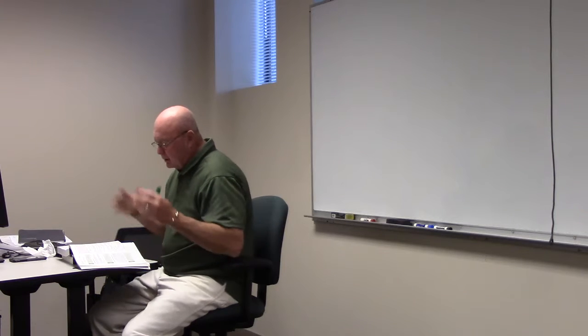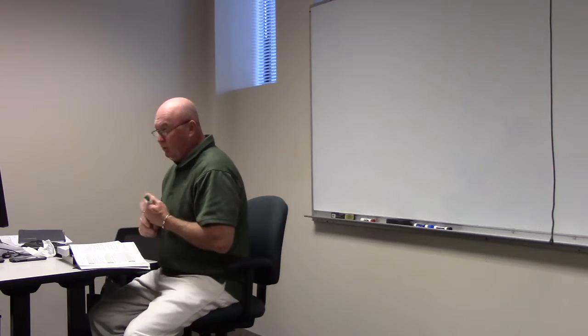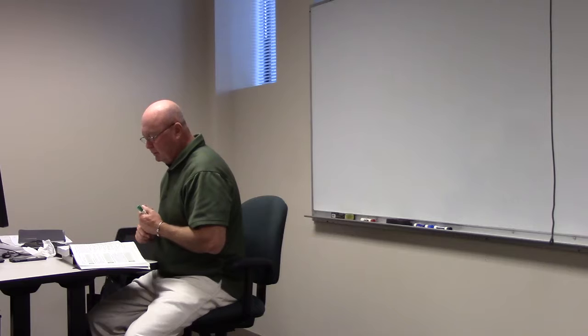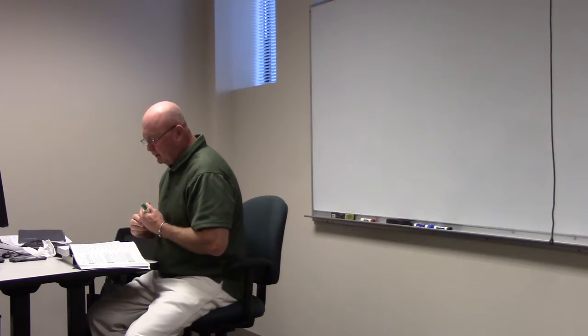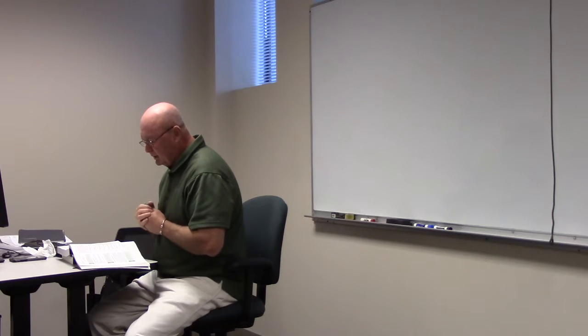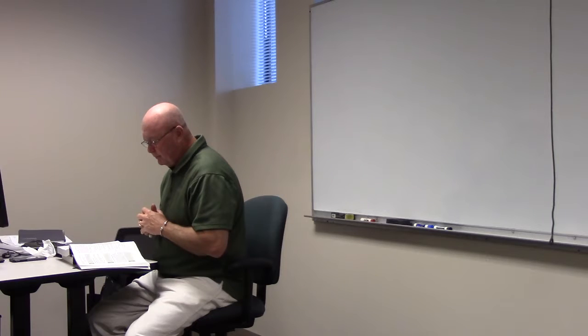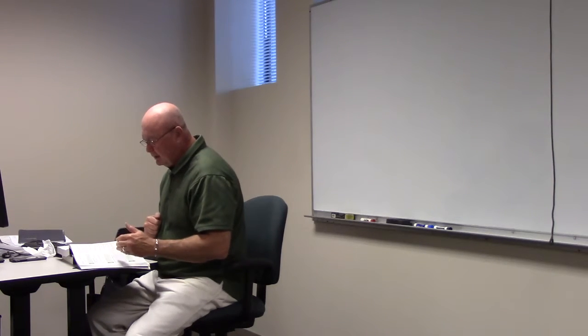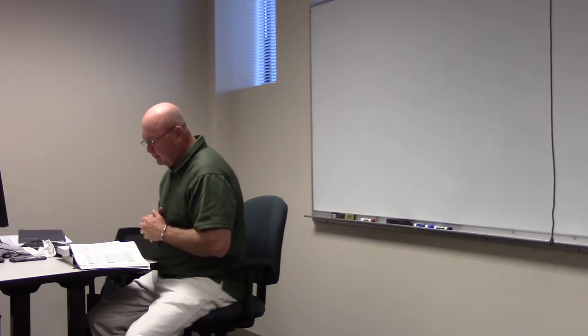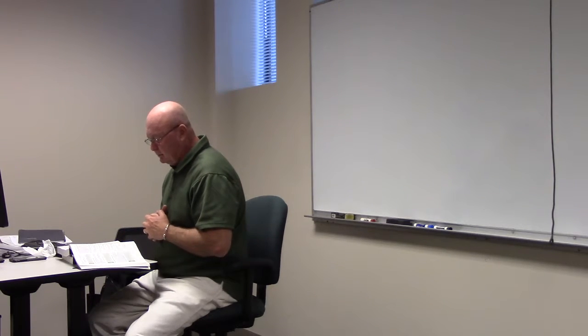It tells me I got a small store. I got show window in the front, which is typical, right? Yeah. Storage area has 4 general purpose duplex receptacles, while the retail area has 14. 2 floor mounted receptacles for a total of 16. These combined with the storage area receptacles bring a total to 20 outlets that do not supply continuous load. What are the conductor sizes for the service if the 120/240 single phase will be used?